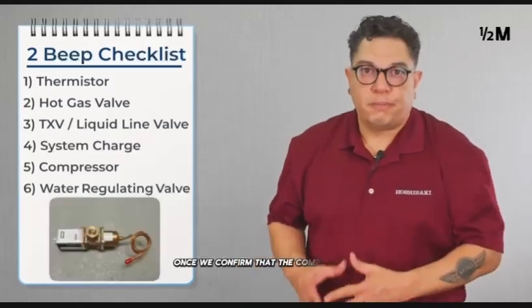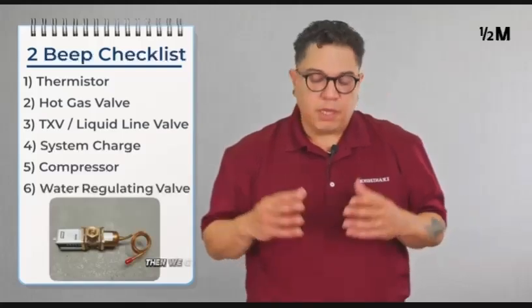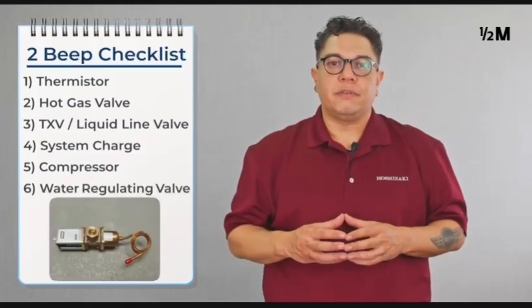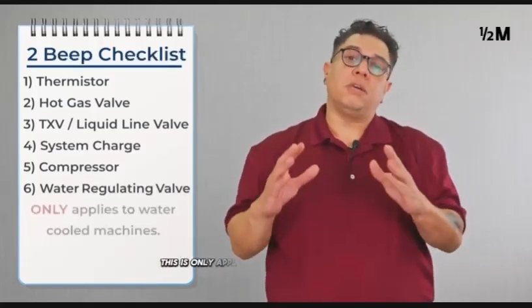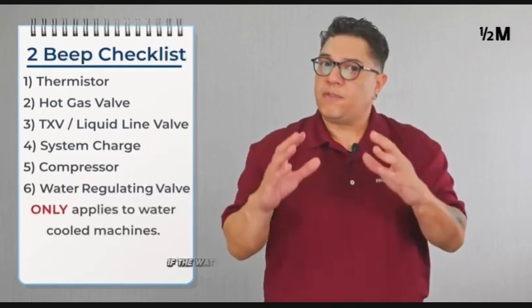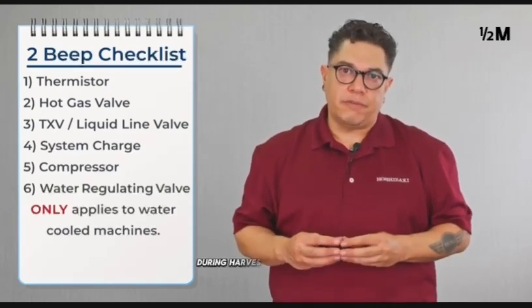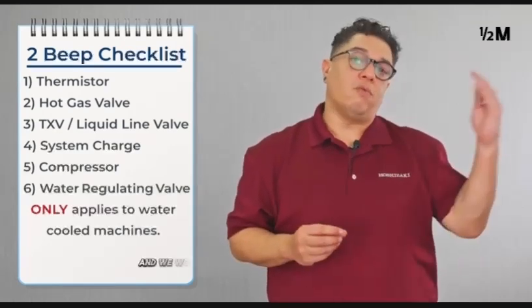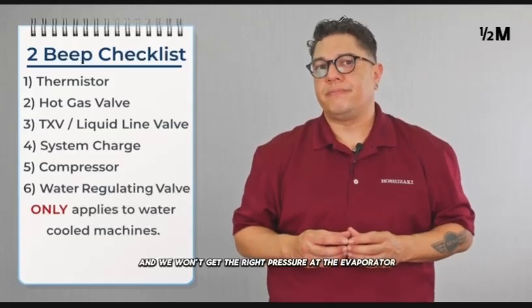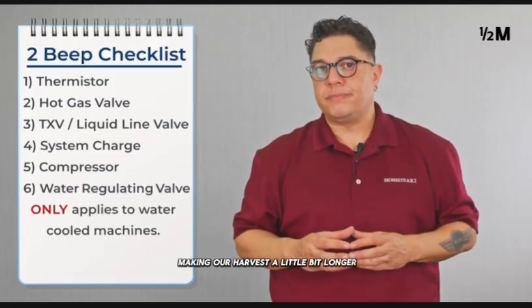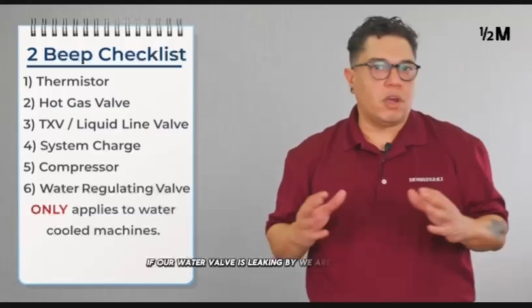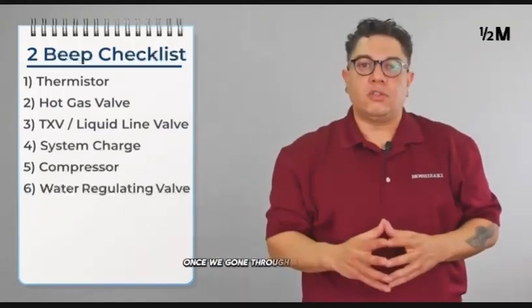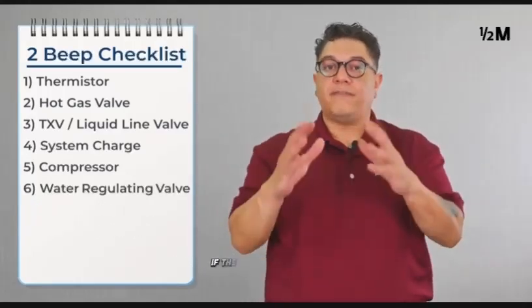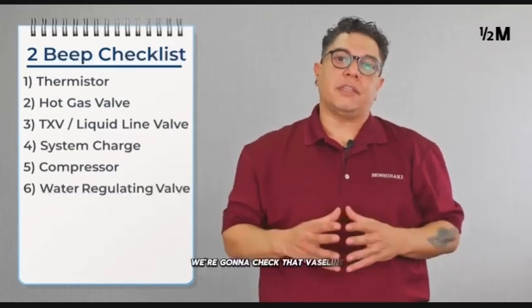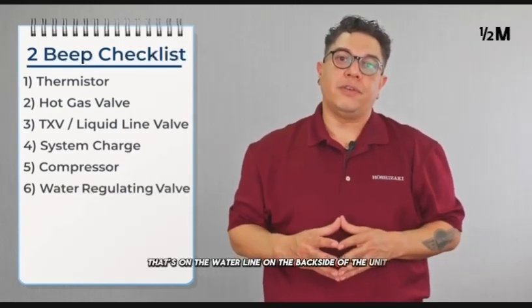Once we confirm that the compressor is working properly, then we can move on to the water regulating valve. Now, the water regulating valve only applies to water-cooled machines. If the water regulating valve is leaking by during harvest, it'll cool that refrigerant down and we won't get the right pressure at the evaporator, making our harvest a little bit longer. If our water valve is leaking by, we are replacing it. Once we've gone through all the steps, if the alarm comes back, we're going to check that valve that's on the water line on the back side of the unit to confirm if we have hot water migration coming into the machine.